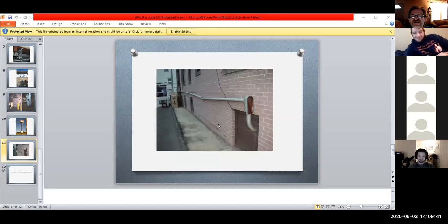So when you start getting into bigger sizes, instead of having a bend, they call these things LBs, and they've got a little unscrewable cover to it so you can route the cable through it, because the cable, even though it's stranded, it's still pretty stiff. But A, that cover's gone, and B, your supports are completely missing. And you know that pipe's got to be cutting into the insulation over there.